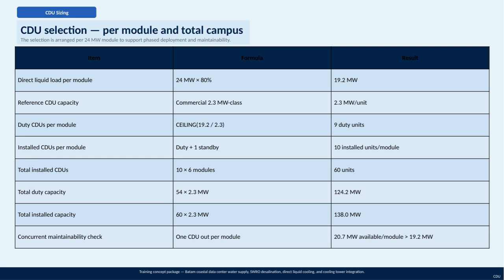The key parameters start with a direct liquid load per module, calculated as 80% of the 24 megawatt module capacity, resulting in 19.2 megawatts. For the CDU capacity, we're using commercial units rated at about 2.3 megawatts each. To meet the 19.2 megawatt load, we need 9 CDU units operating per module. However, to ensure reliability and maintainability, we install one additional standby unit per module, bringing the total to 10 units installed per module. Since there are 6 modules on campus, this totals 60 installed CDU units.